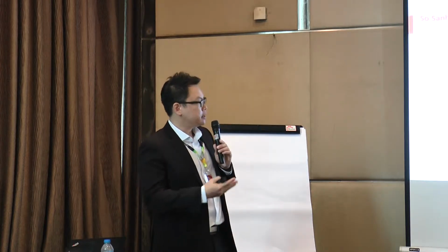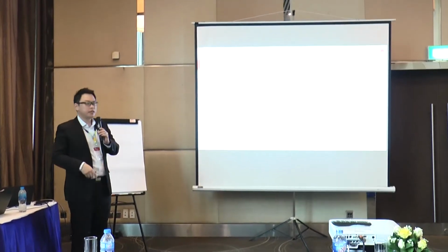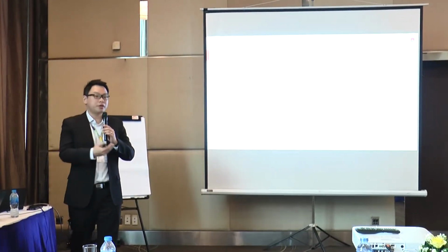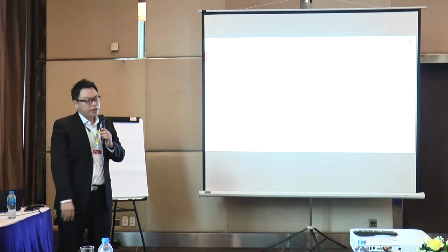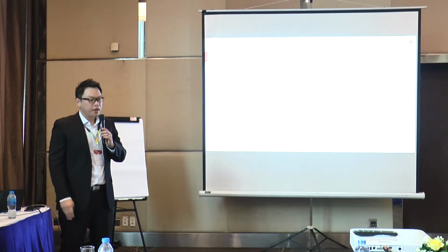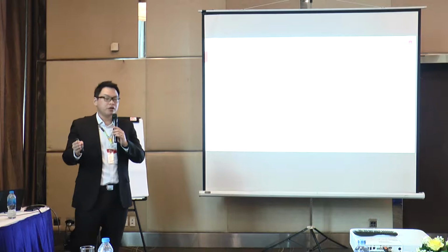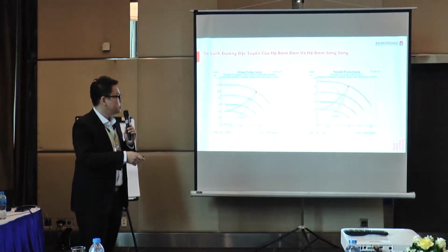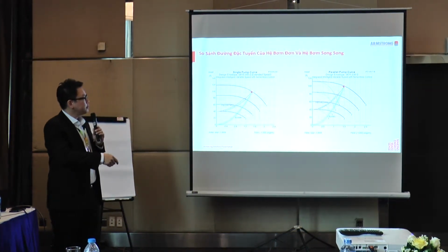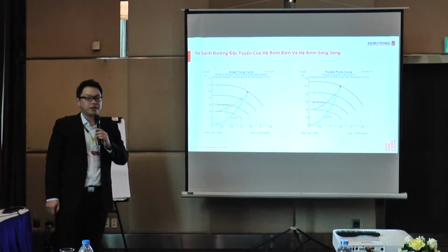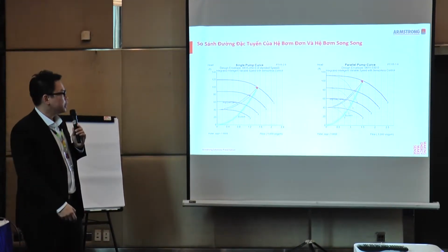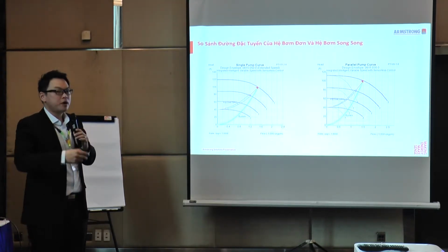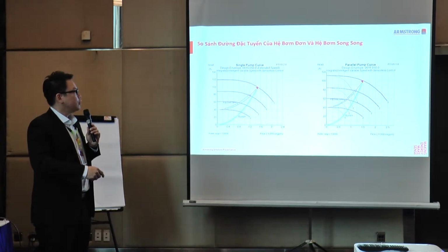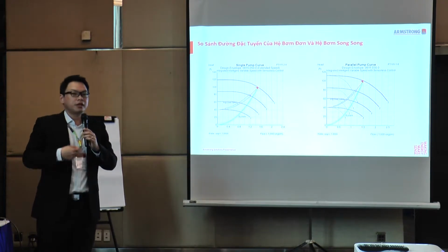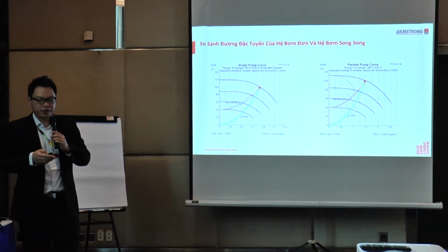And again, this is just some background on the single pump. The graph on the left-hand side is basically a system where 1 pump is in operation, or the system is designed with 1 pump. And when you design your system with 2 pumps in parallel, this is how it looks. Okay. So at every point, capacity doubles up. Also take note that each pump is of the same size, and whenever you reduce to a single pump, you still have to intersect the system curve.